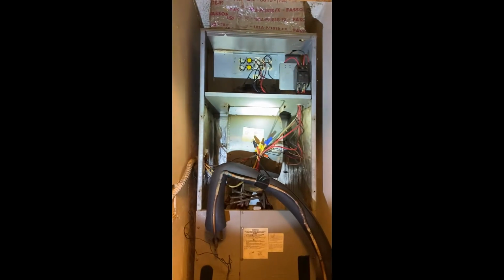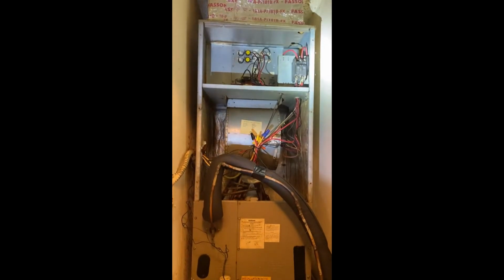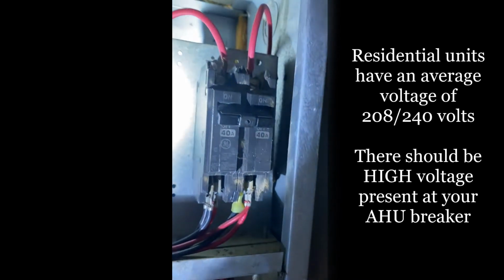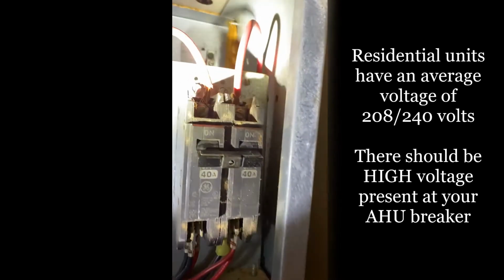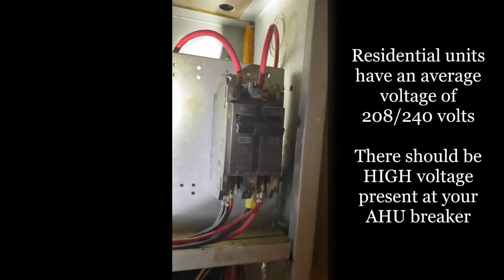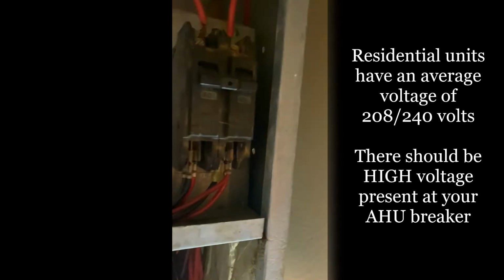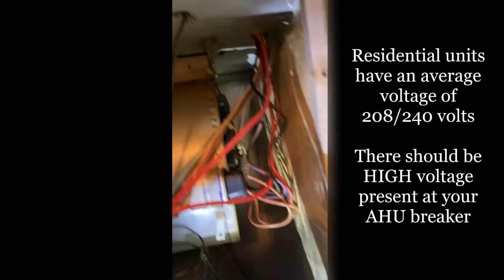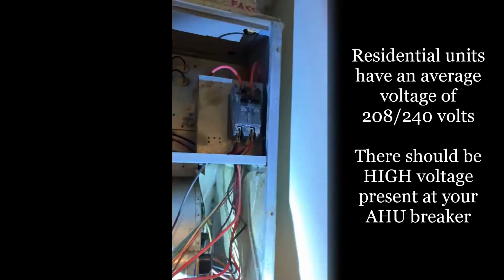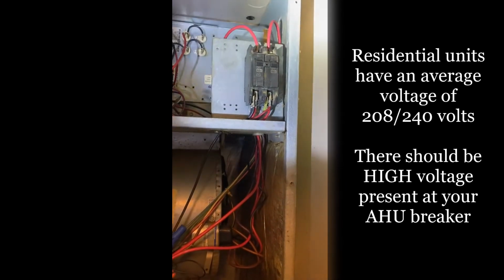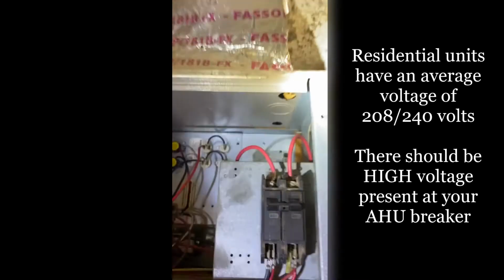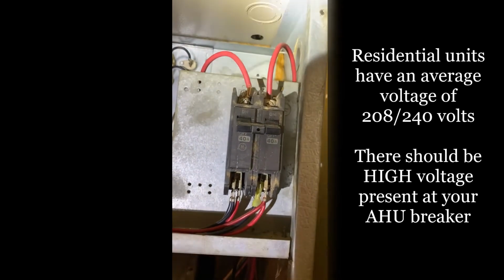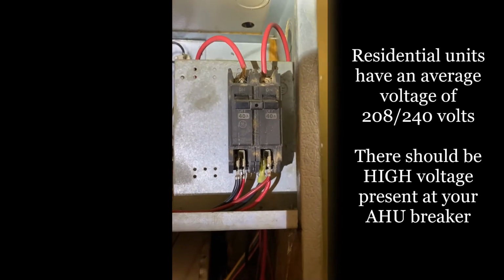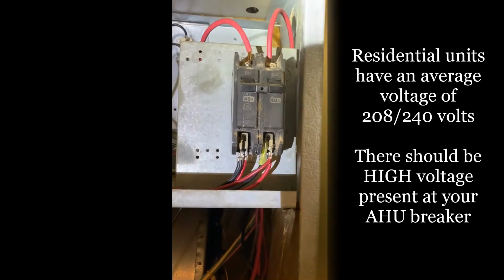All right, so we got our cover off. Your power's off. And we're gonna go to where our main voltage comes in, which is always the breaker here. You can see the 2 main lines. On a normal unit will have 208 or 240 voltage. That is an average unit. Just about every home has the same voltage. All right, and you check between the 2 lines. I'm gonna show you. And this will tell you, do we have high voltage coming in or not? And if you do, great, we'll continue. And if you don't, I'll tell you what to do.